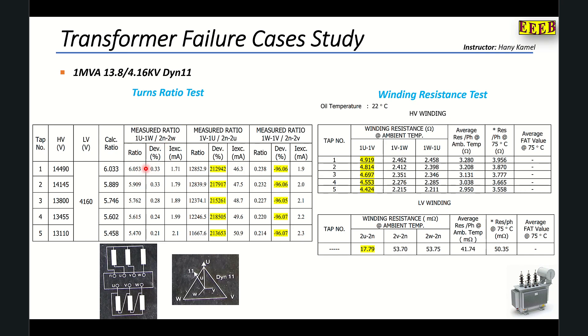This is the measured ratio, this is the error, and this is the excitation current. You can see the error is within the limit, so it is acceptable.